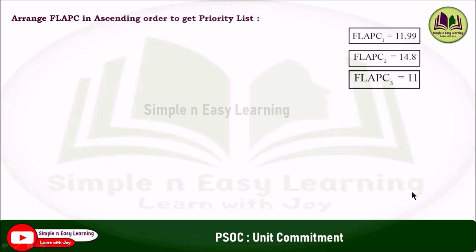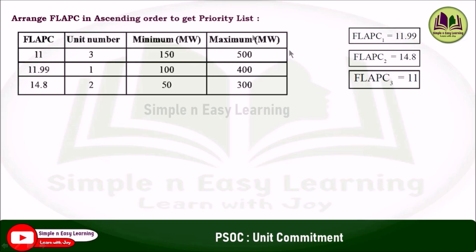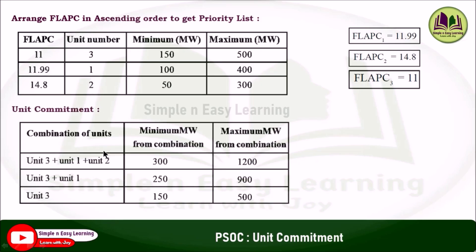Arrange the FLAPC values in ascending order to get the priority list. In the table: 11 (unit 3), 11.99 (unit 1), and 14.8 (unit 2). Write the corresponding minimum and maximum limits for each unit. The priority order is: first priority — unit 3, second priority — unit 1, third priority — unit 2.